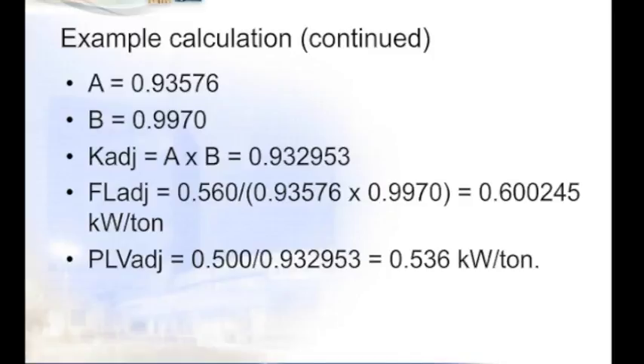When I calculated this the first time, I went through and just took the first six decimal places, and it gave me these numbers. I had somebody check the math on a different calculator, and they chose to not round anything, and the numbers came out slightly different. The A value was 0.928111. The adjusted K came to 0.925326. The full load at 0.605 instead of just 0.600, and the IPLV came to 0.54035. So while it may not sound like much in the thousandths of a number, since that's what the table lists it as, it'd be best to be as accurate as you can be, particularly when you talk about these requirements with the manufacturers. So all this is to say, be wary of rounding or truncation too early in the calculation, because it may not give you the exact numbers that you want.